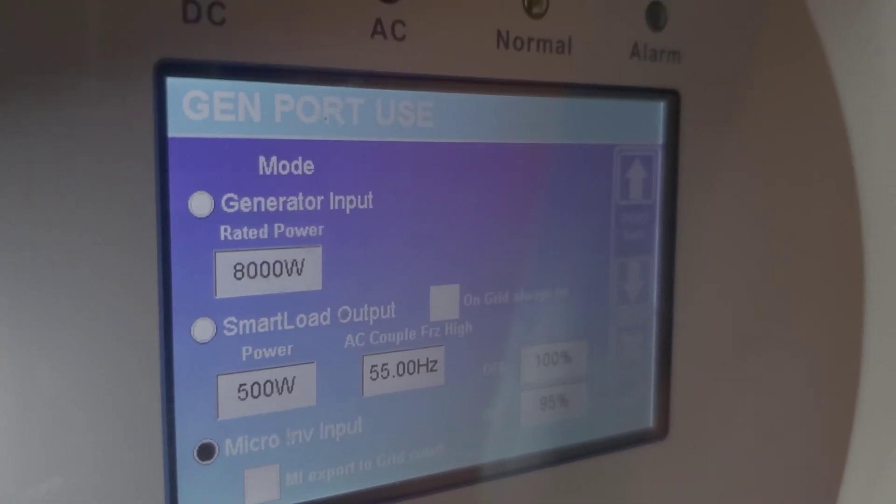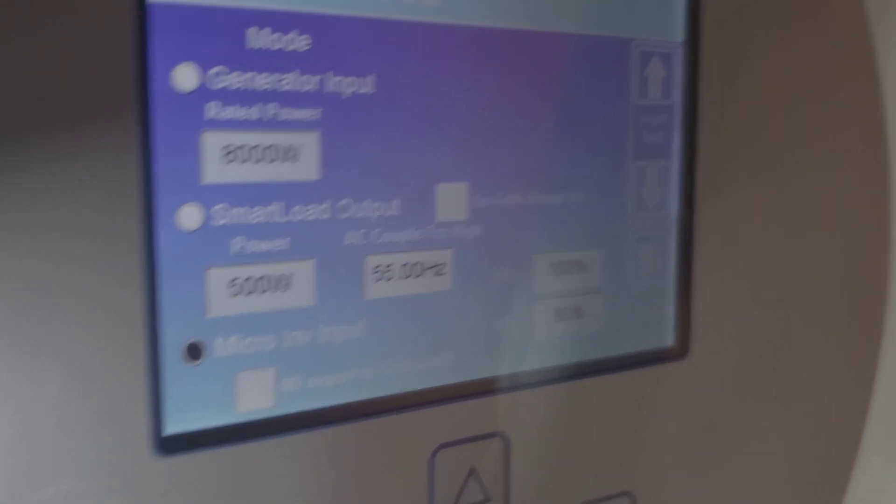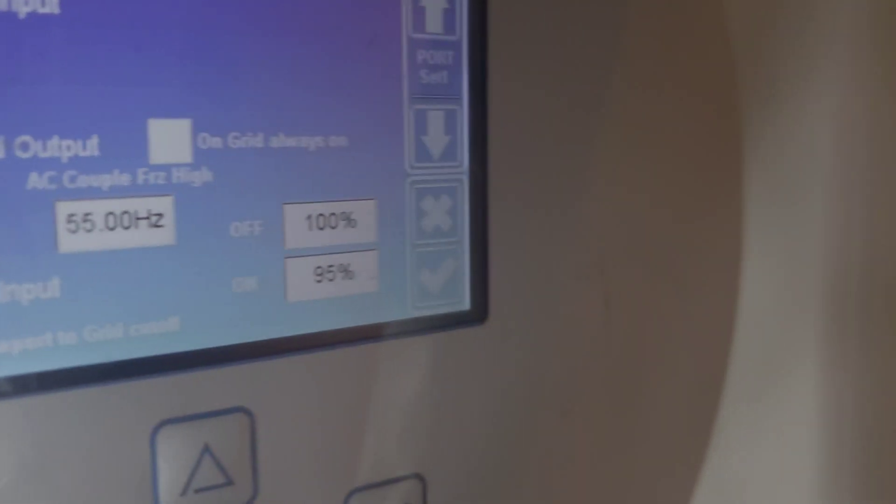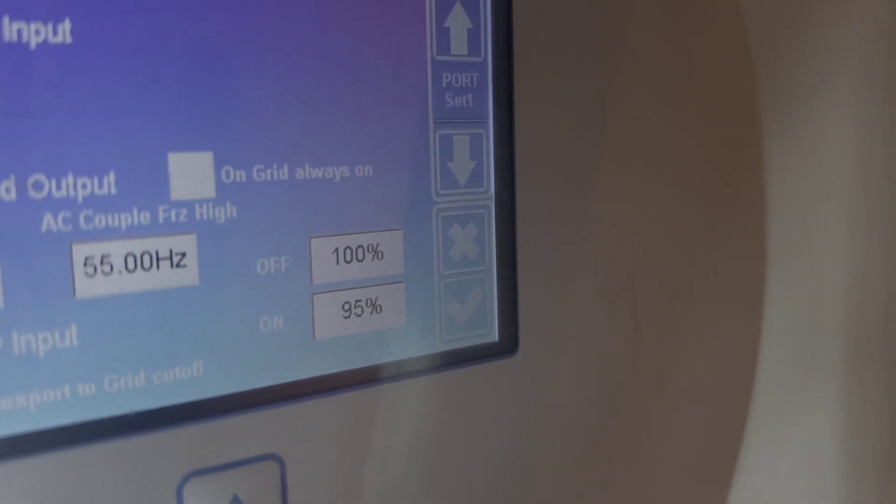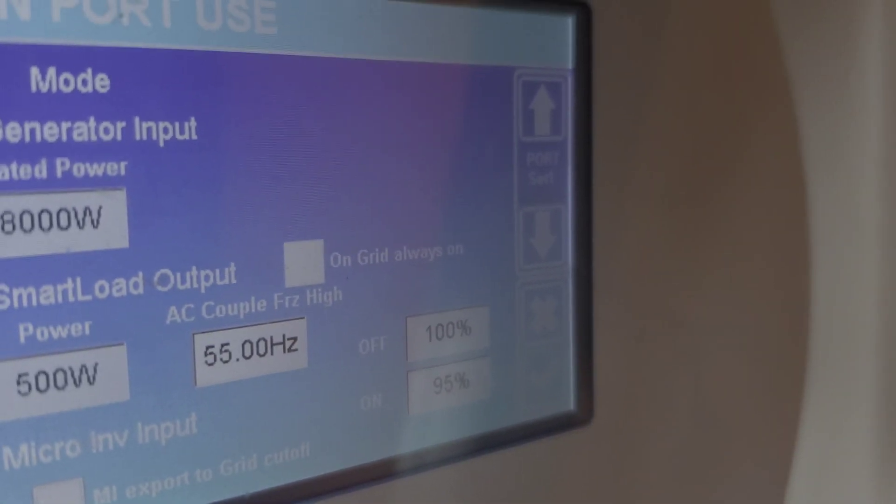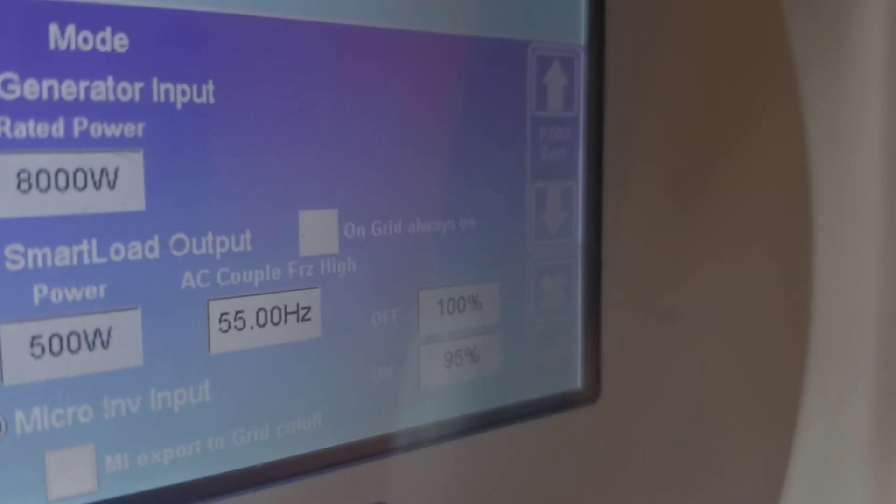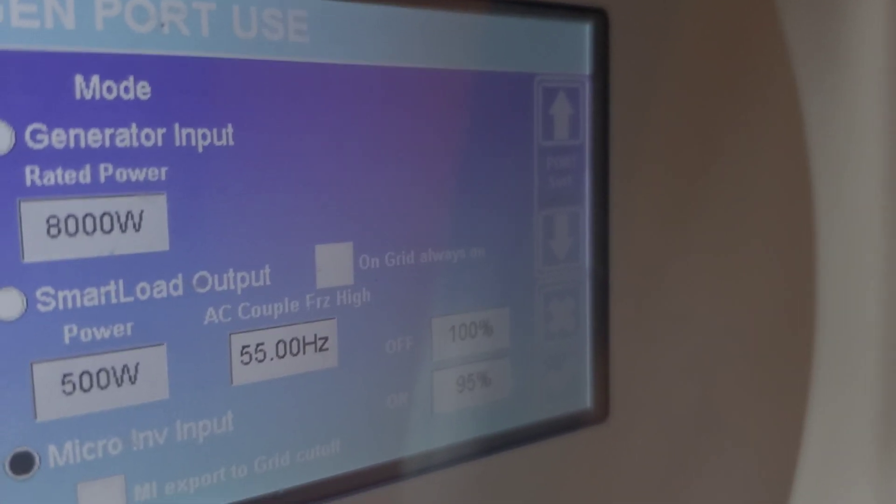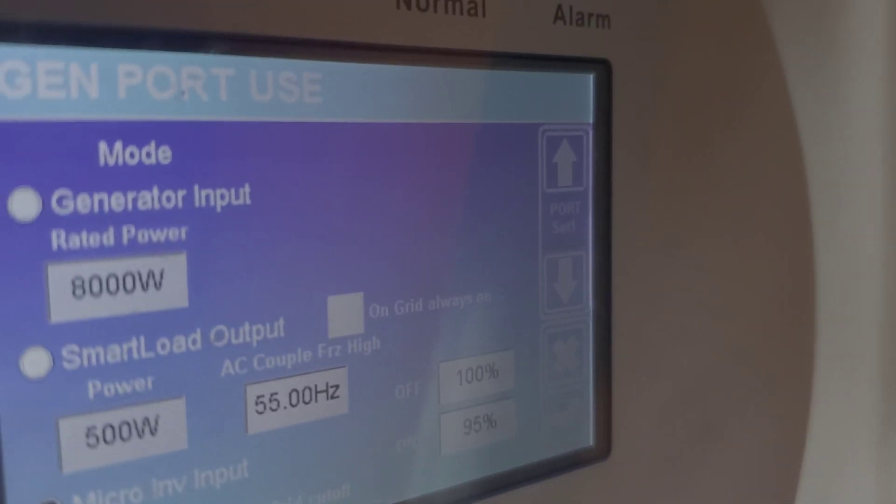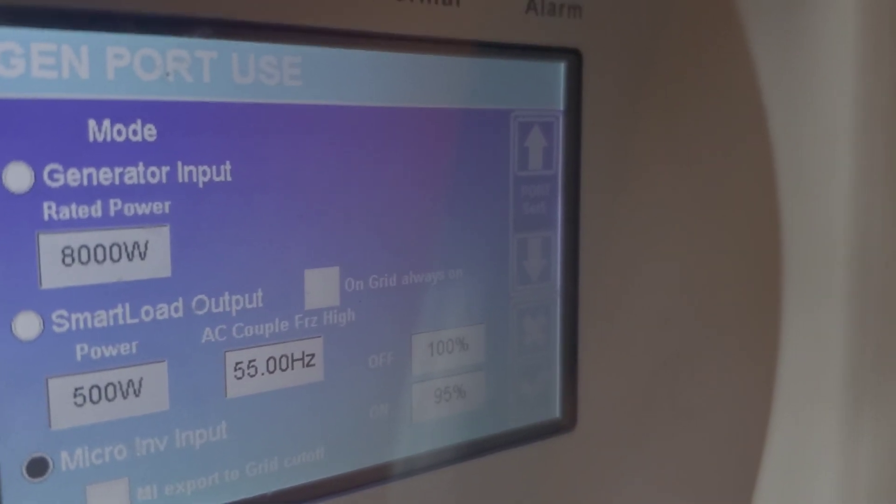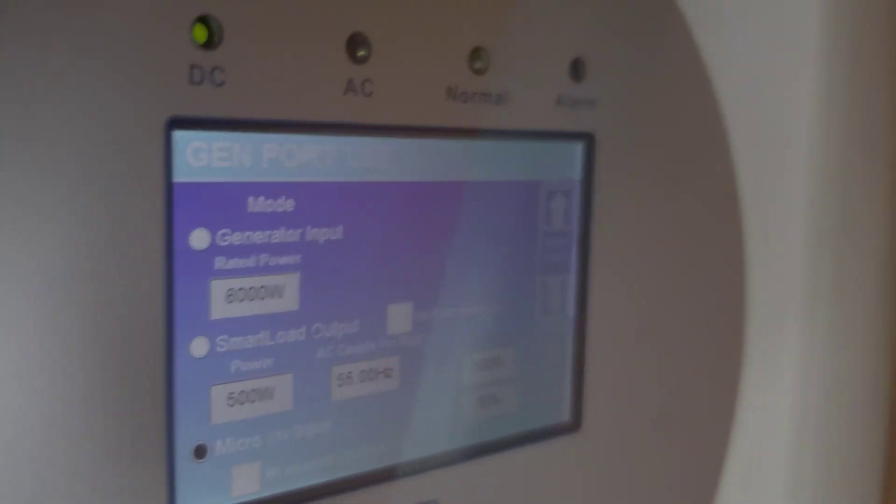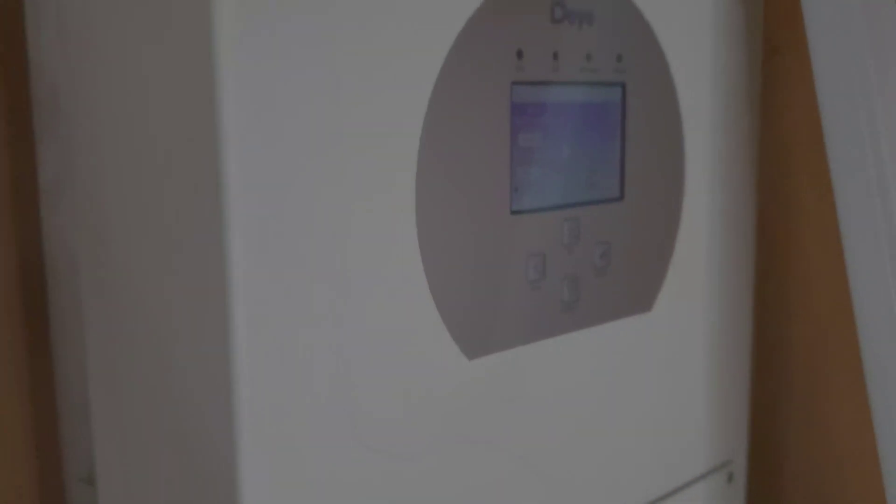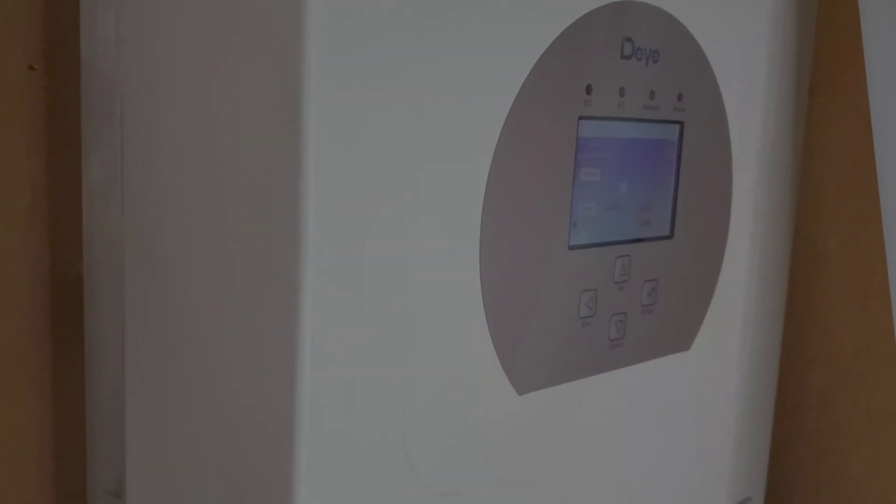I'm using it as a smart load output by using it as a micro inverter. And if you notice, the micro inverter comes on at 95% and switches off at 100%. The 95% is the highest I can go, I can go lower but I cannot go higher. And then the 100% is where once the batteries are full you want the grid-tied inverter to go off.